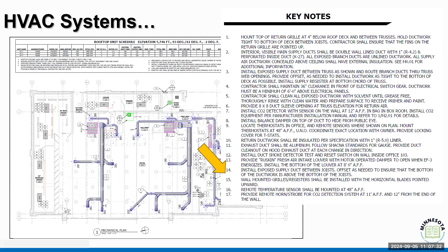on actual plans was I had a building, a larger building. It was a police station, and one of the conversations with the number of pieces of equipment that were in that building, we needed to have a proper sequencing of those controls so that we didn't have cooling equipment operating at the same time as heating equipment for the same space, right? To where we're creating a potential humidification problem, right? So it's all about making sure that we evaluate the types of controls, the location of those controls, and the code provides us a huge section of code to dictate or to define, guide those conversations.